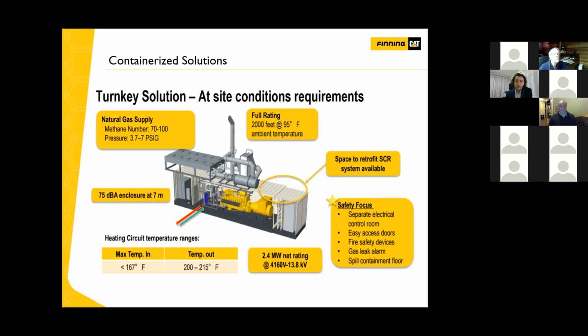This particular site had extra space for a future SCR and some site-specific temperature requirements we had to chase. In this case, the generator set net rating was about 2.4 electrical megawatts from a Caterpillar G3520H, a high efficiency generator set. We also note special safety focus items: a separate electrical control room, easy access doors, fire safety devices, gas leak alarms, and spill containment floor.